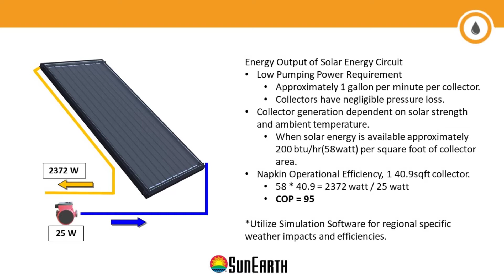So if you take that with a nominal 25 watts per panel, when you get to larger systems, that can go down dramatically to 5 or fewer watts per panel as far as required pumping power. But if you're running a basic back of the napkin COP calculation, you have 58 watts per square foot for a collector, for a 4 by 10, or 40 square foot collector, 25 watts, and a COP of around 95. Right? So the amount of energy that you're putting into a solar thermal system for the amount of energy you get out is pretty tremendous. And that's really a huge advantage for a lot of heating systems, where solar thermal technology can pair well.